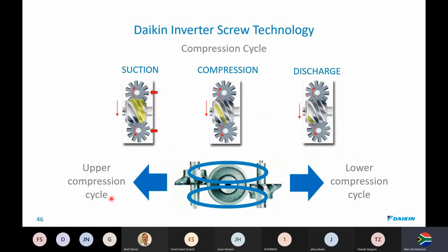But anyway, let me show you why I said we oppose these geometries: besides balancing radial and axial forces, it also allows us maximum compression. So we use virtually 360 degrees of the rotor for compression. So we compress on the top with this gate and we compress on the lower half of the rotor with this gate rotor. So upper compression as well as lower compression, and we discharge radially through both these volutes.